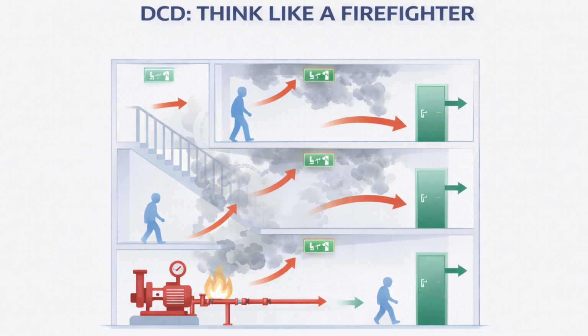Firefighters do not have time to search for systems or interpret drawings. Everything must be intuitive, accessible, and reliable. This is why Dubai Civil Defense expects fire systems to be designed for use, not just approval. A system that looks good on drawings but fails in an emergency has no value. When you design as a firefighter, your layouts become simpler, your systems become clearer, your coordination improves.